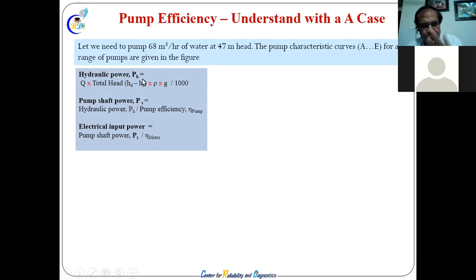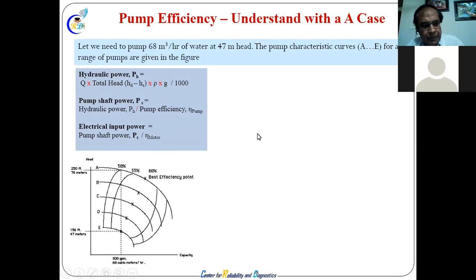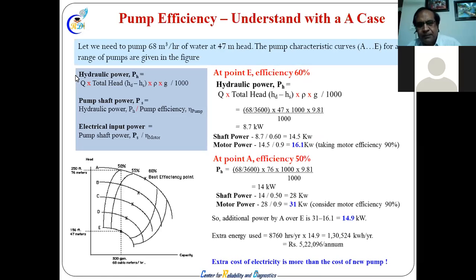I don't know whether I told it the correct way in the previous minute or not. Okay, so hydraulic power and shaft power, that's why efficiency comes into the picture. In this efficiency picture, suppose we put in 100 kilowatt of electricity, we get a shaft power of maybe 95, and accordingly the hydraulic power at the flow, which is our efficiency point, is much less than that. That's the idea. At the efficiency point it is 60%. This is the best efficiency point, 60%. If you go to any side, there will be efficiency loss.